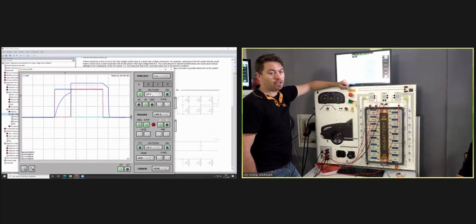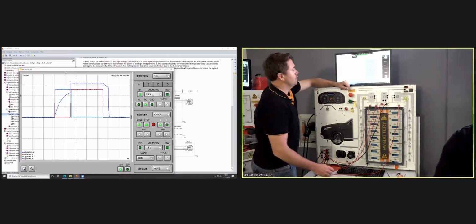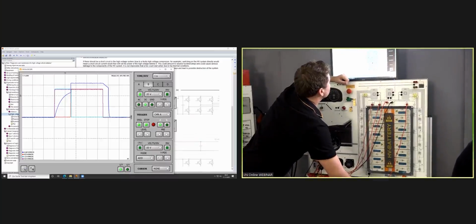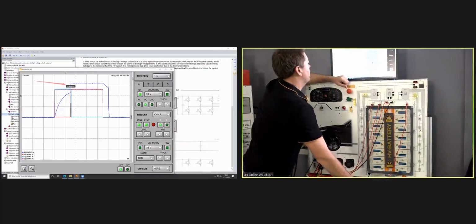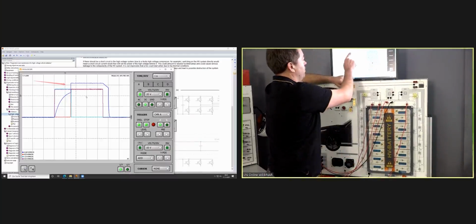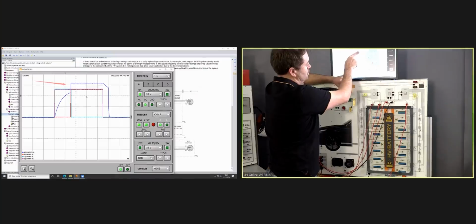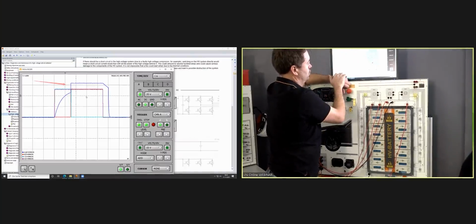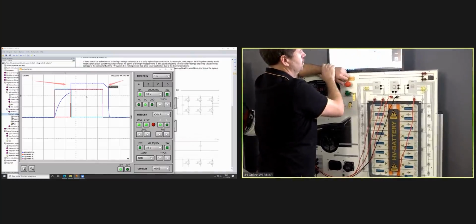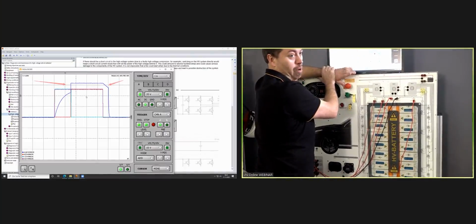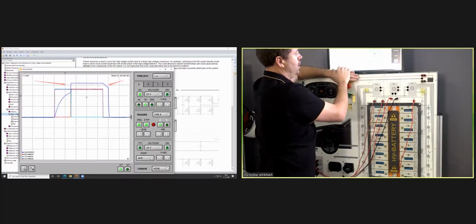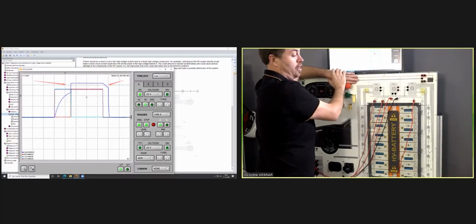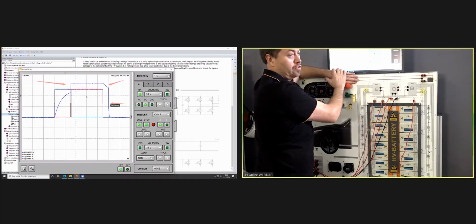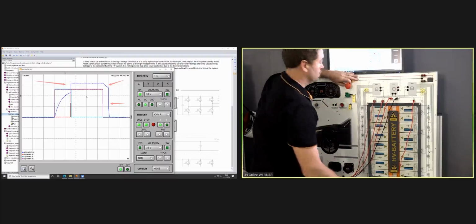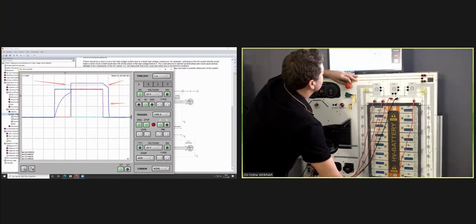And then the high voltage comes up. So let's bring this down—look at that. Once we're at high voltage, we can see this shutdown: both relays have turned off. We've got a slow discharge going on there, that's called passive discharge, and then straight away we see the voltage drop down, which is active discharge. There are various methods for showing that, but this short diagram tells you a lot.